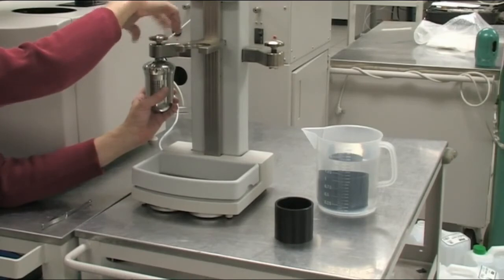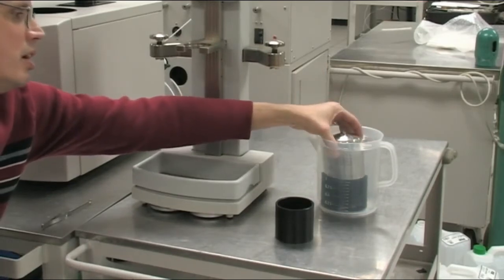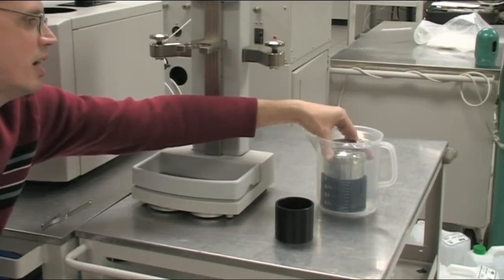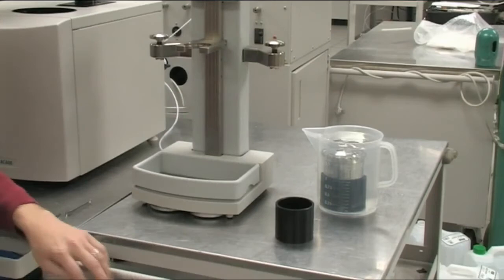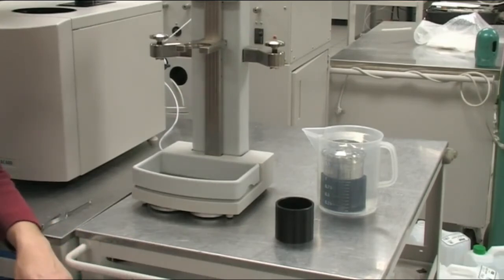The next thing you want to do is disconnect the vessel, slide it out, and put it in a container of water. Let it sit for a few seconds and watch to see if you have any bubbles forming. This is our leak check, and we want to make sure that we don't have a huge amount of bubbles coming out of the vessel.